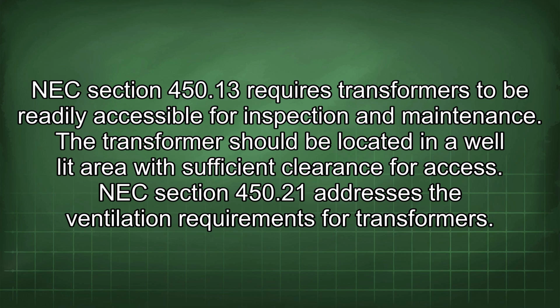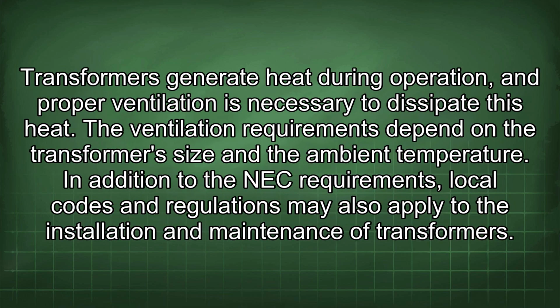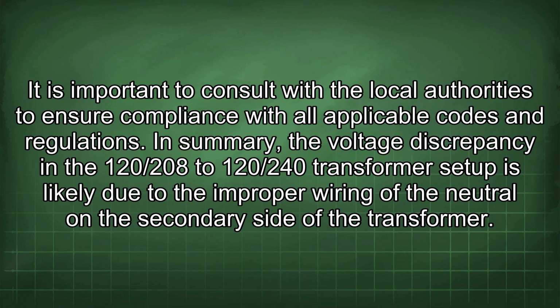NEC Section 450.21 addresses the ventilation requirements for transformers. Transformers generate heat during operation, and proper ventilation is necessary to dissipate this heat. The ventilation requirements depend on the transformer's size and the ambient temperature. In addition to the NEC requirements, local codes and regulations may also apply to the installation and maintenance of transformers. It is important to consult with the local authorities to ensure compliance with all applicable codes and regulations.